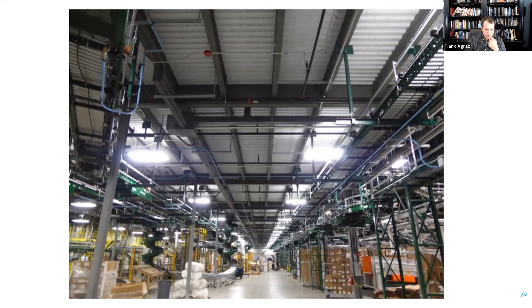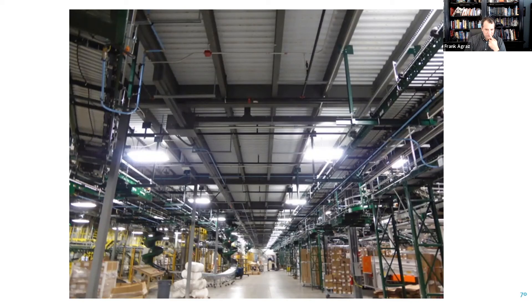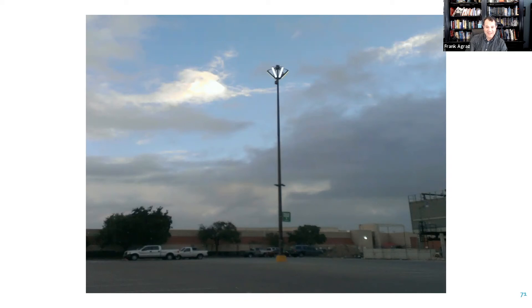Let's wrap up with some interesting examples — 'What Were They Thinking?' First example: why did they put the lighting above their racking system, and why spec out a high bay with uplight in that situation? There are a lot of watts wasted. In the architect world, when building new construction, the lighting design sometimes doesn't talk to the folks putting in the equipment and information gets lost. Another example: retrofit people do stupid things and customers sign off on it — we can do much better. In a retail space, someone thought it was great to put high-pressure sodium, perhaps because their lumen output looked higher on a spec sheet. Ironically, the good lighting was in the back of the house where the cashier is. With a black ceiling and poor little cove lighting doing its best, that's not really getting the light out. Sometimes there's too much light — a classic case for redesigning and removing fixtures.